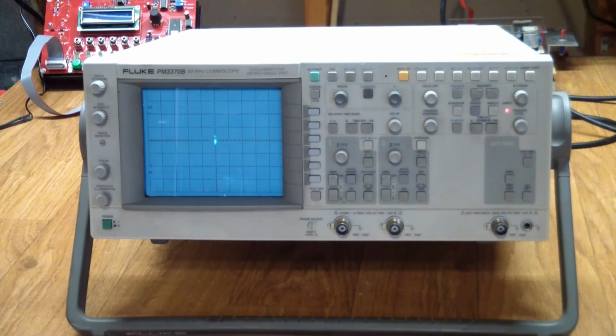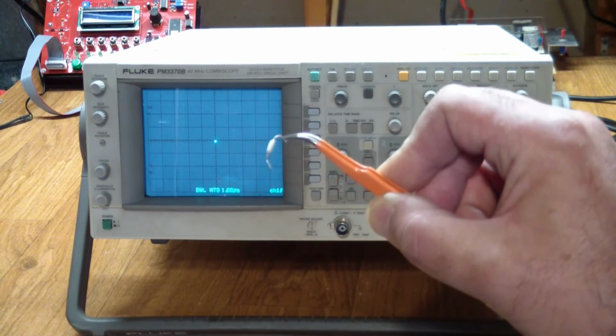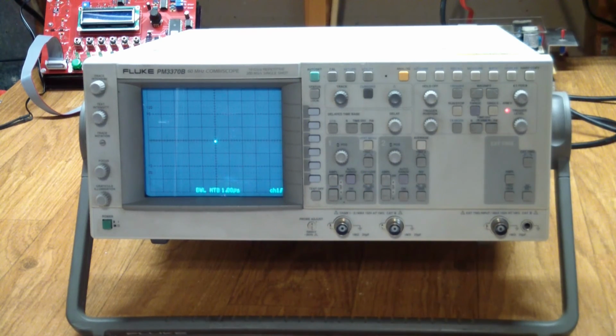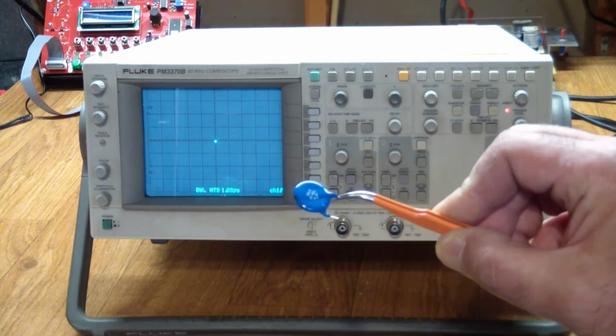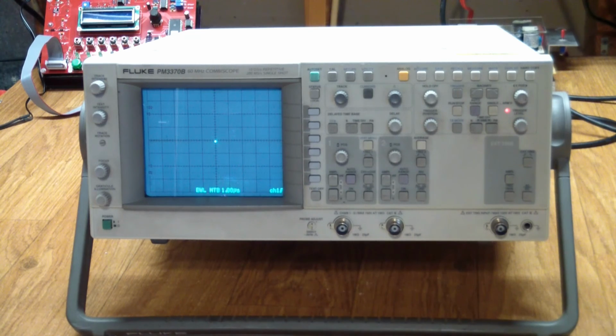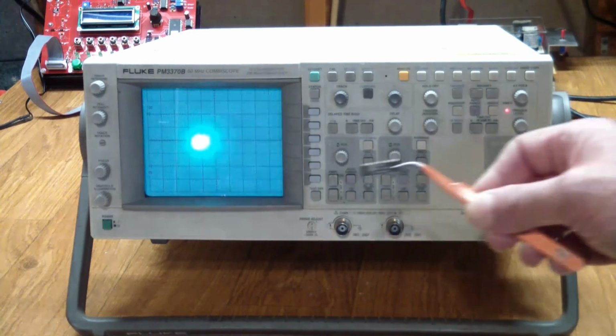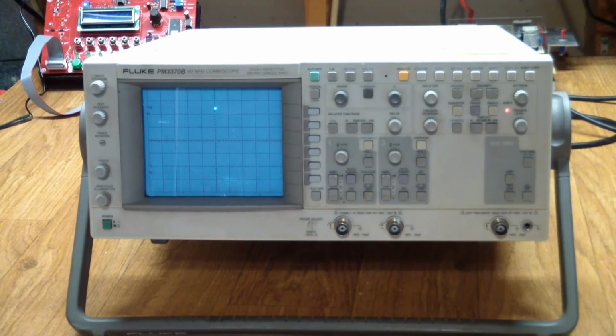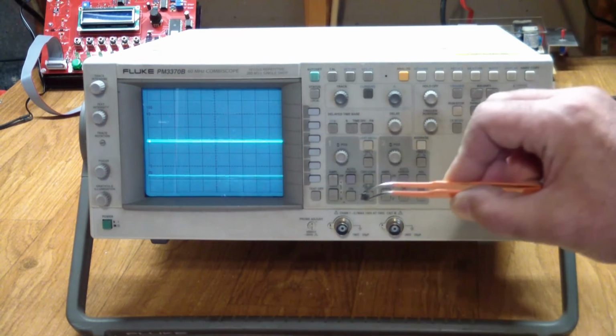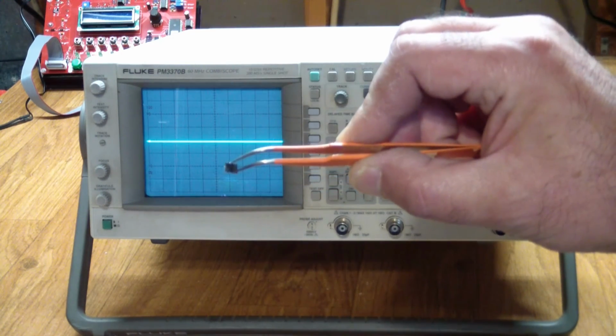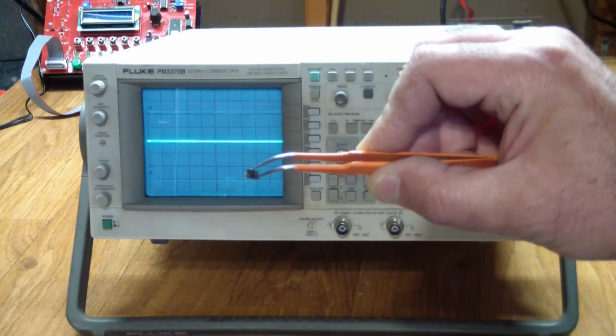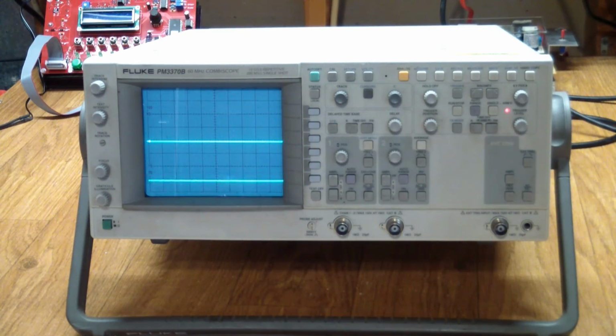And to sum up, what we did is we replaced a bunch of parts. One was the rectifying diode for the cathode voltage. We replaced 3 capacitors also in the high voltage area. Then we found that the quad DAC was bad. Subsequently replaced that. Then the opamp was bad. That was generating the proper voltages for both the fan speed and the Graticule illumination. So this got replaced.